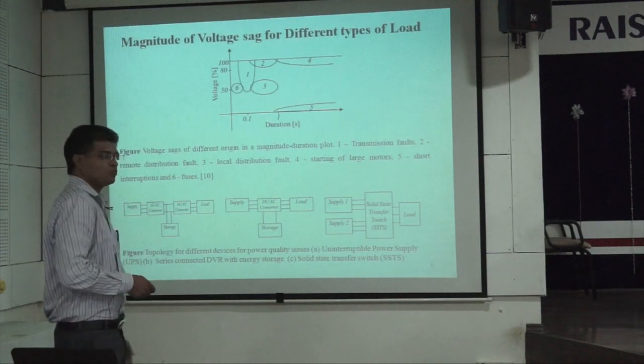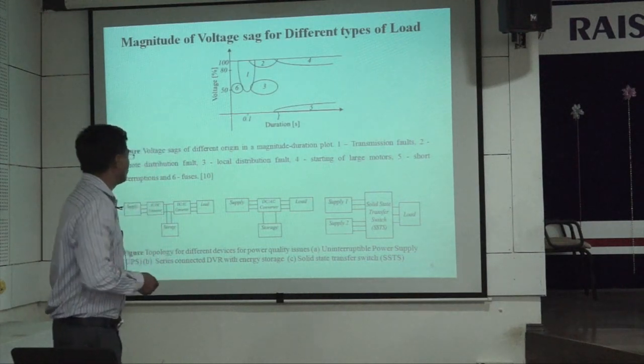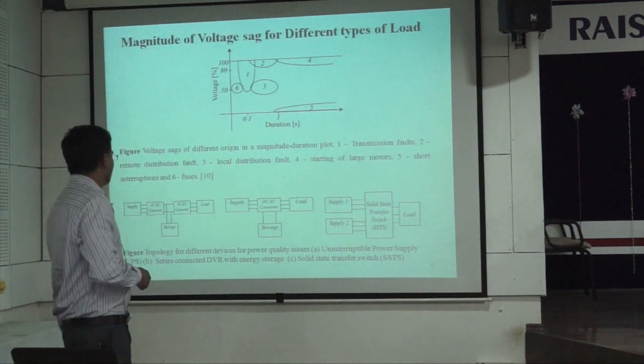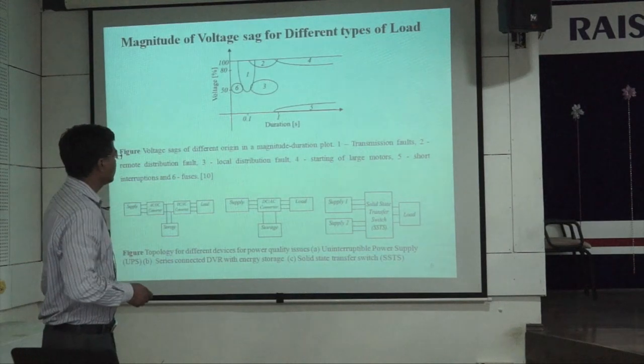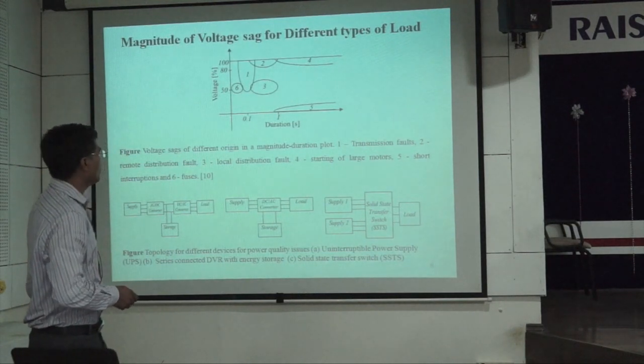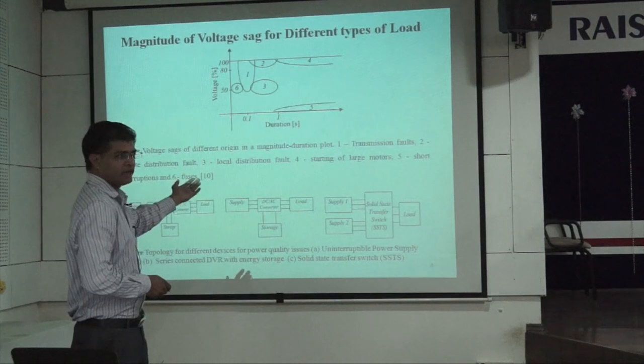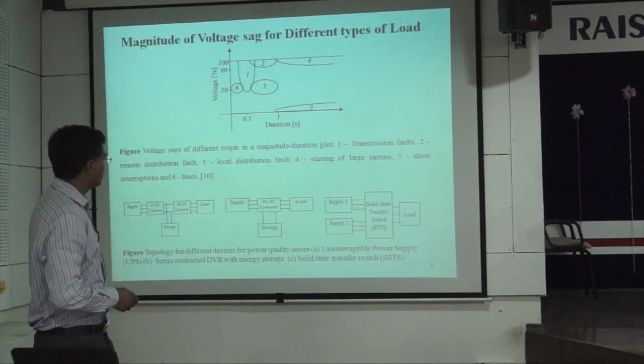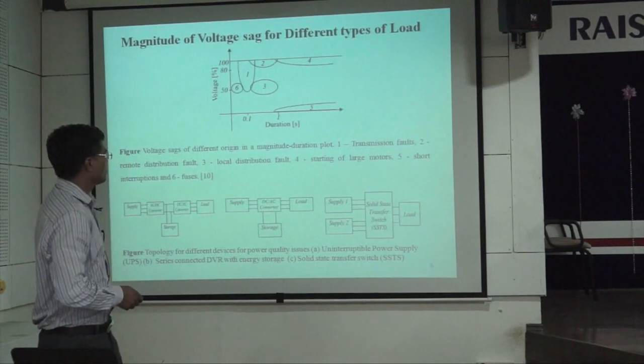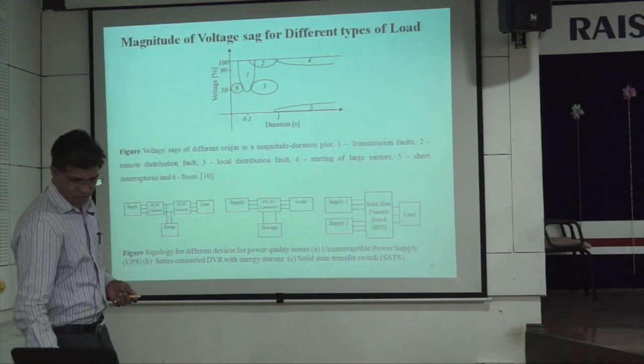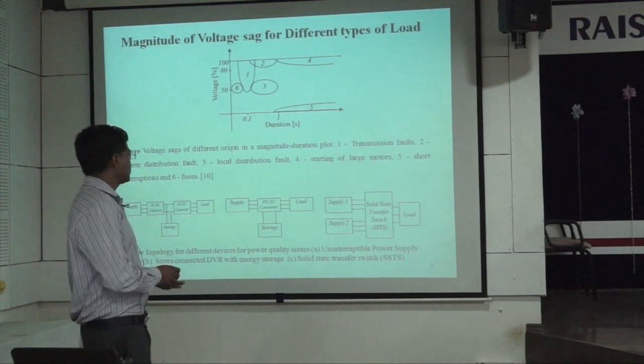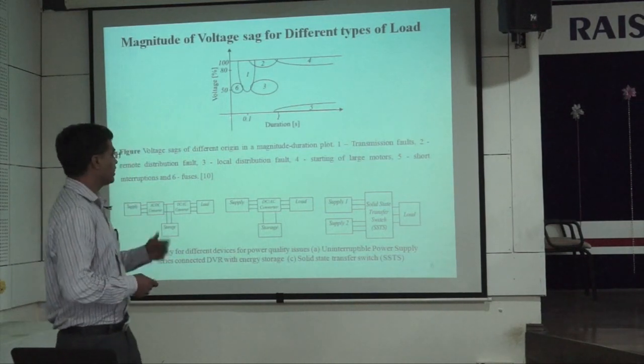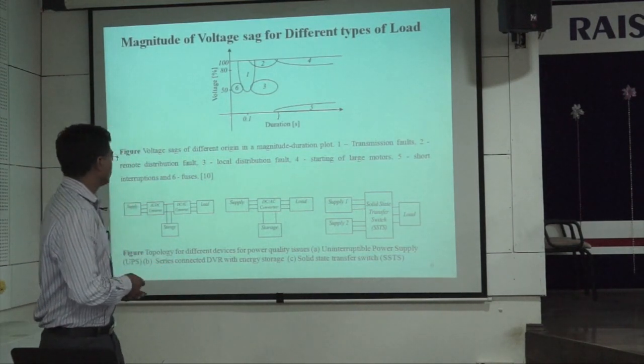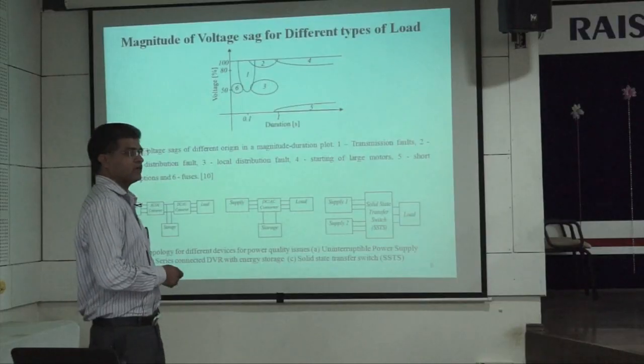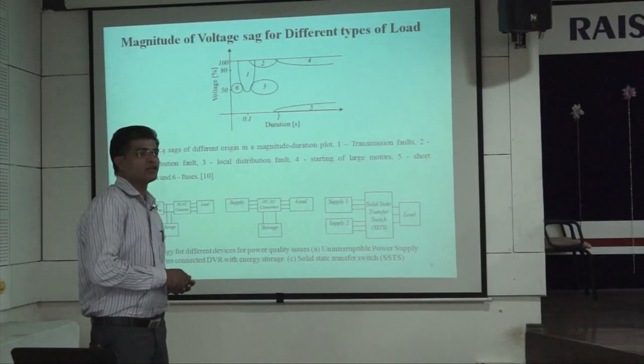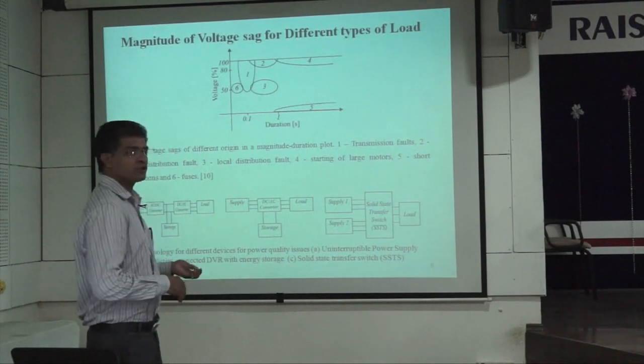There are various devices used for power quality improvement, like the UPS, like the DVR or STS. Whenever there is a fault, the supply line is switched from the sagged voltage line to the other normal healthy line. For that, we have to use the solid state transfer switch. But there are various considerations about these devices. Higher rating devices are used, like the StatCom. If you use the StatCom at shunt for the voltage control, then the rating of the StatCom will be much higher as compared to the DVR.